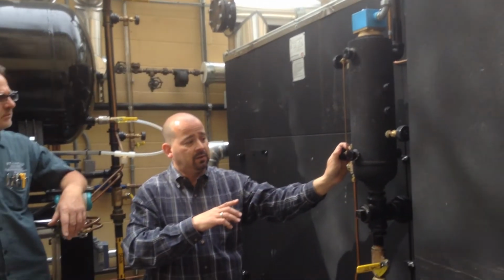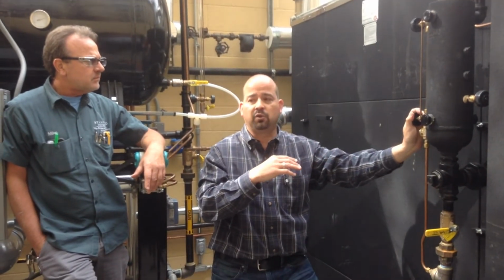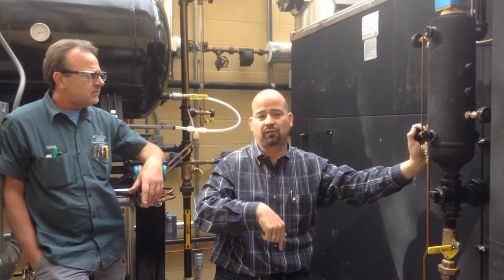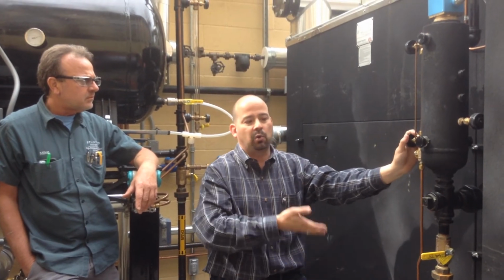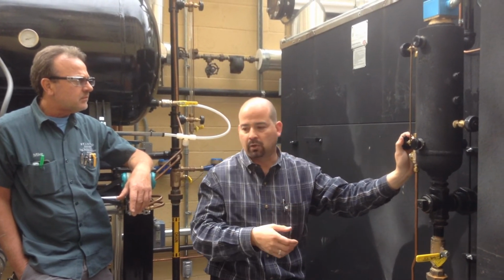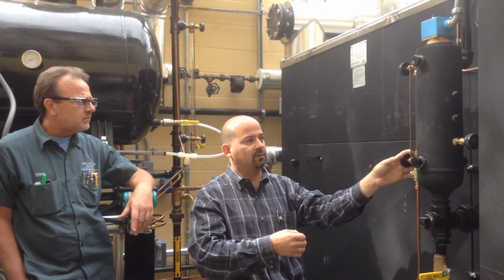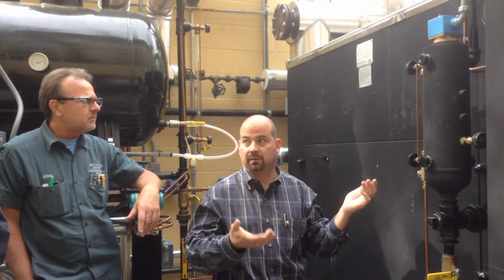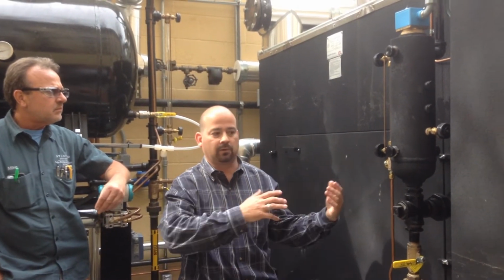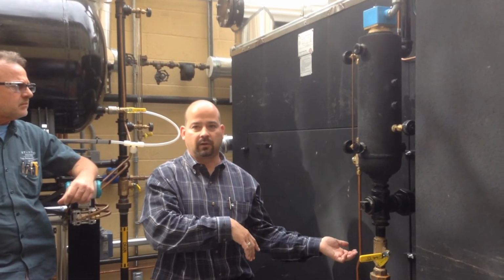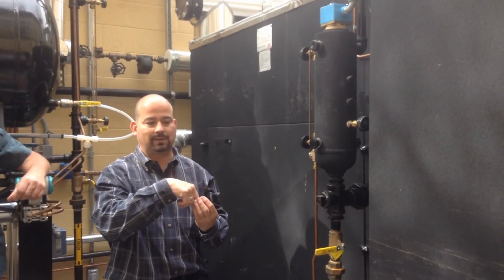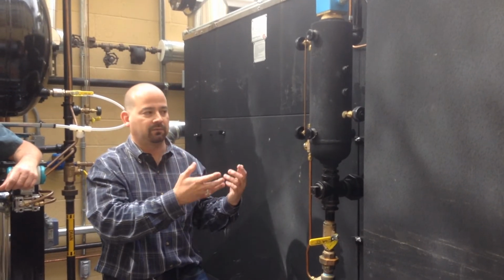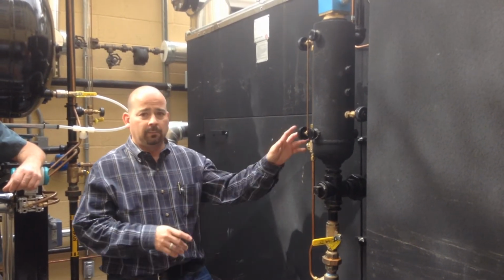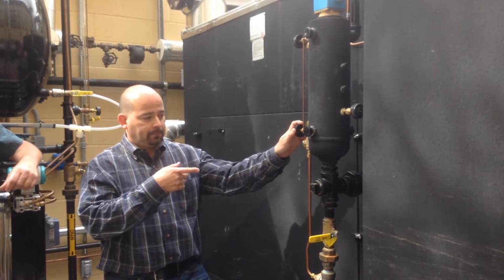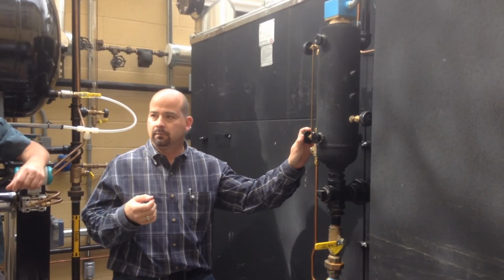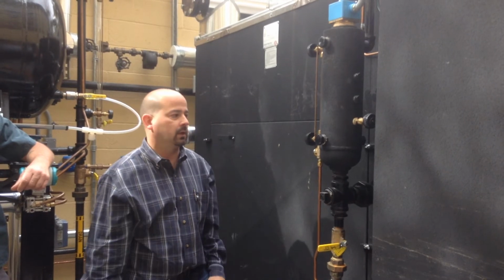And a lot of times when we have water level problems, and it's not unusual to have water level problems after an initial startup, because a lot of times we'll get some coating from the manufacturing of the boiler or from new chemicals or whatever, and it gets like a little slimy coating on it, and it causes the pump to never shut off, or it causes the boiler to go off on low water when it's really not a low water condition. It's just that you're not getting good conductivity on the 1/4-inch probe, so we might have to clean them if that happens. But I know Therma, they did a boil out chemical, so a lot of it should be cleaned anyway.